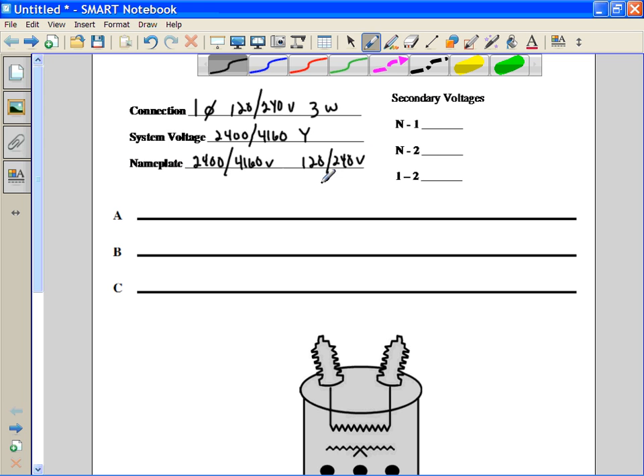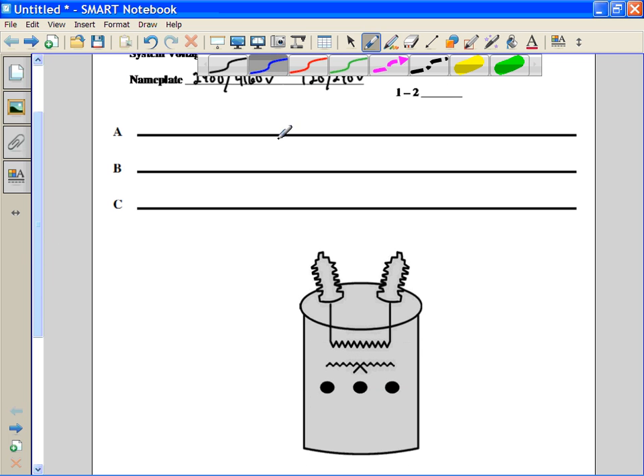So in this case, the nameplate rating actually matches up with the voltage that we actually want to get out of this particular transformer. So once again, as always, let's mark our polarity marks. Again, we'll make the assumption that this is an additive transformer, so the secondary bushings are X1, X2, X3 right to left.